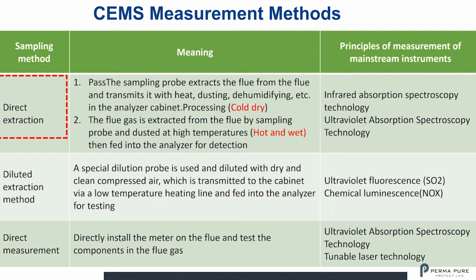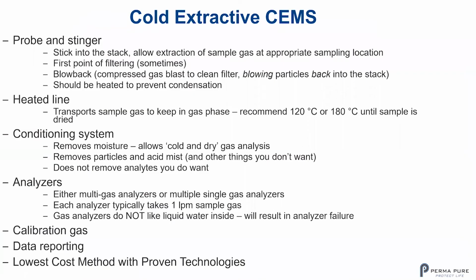There's also the diluted extraction method where you have a dilution probe. And there the principle of measurement is ultraviolet fluorescence for SO2 or chemical luminescence for NOx. And then there's a direct measurement, directly install on the meter on the flue and test the components in the flue gas. That's the in situ. There you use ultraviolet absorption spectroscopy or tunable laser technology. But for the most part, we're working with a cold extractive CEMS, which has proven to be very reliable and cost effective over time. Using this existing validated sample.